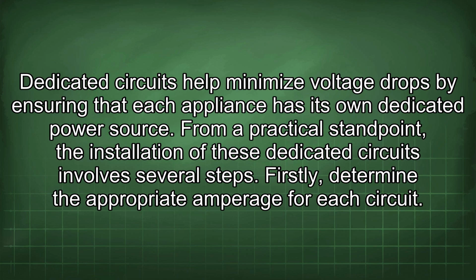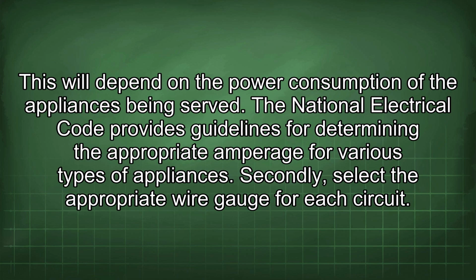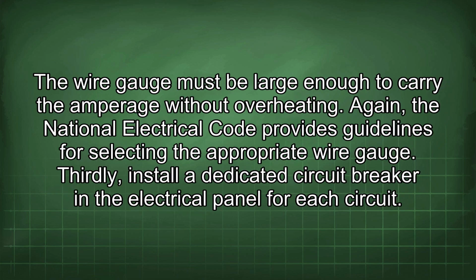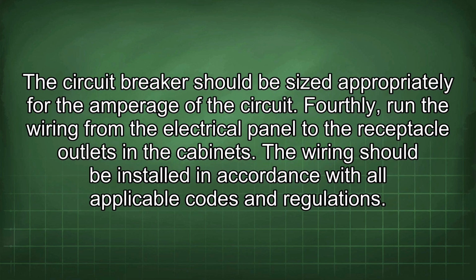From a practical standpoint, the installation of these dedicated circuits involves several steps. Firstly, determine the appropriate amperage for each circuit. This will depend on the power consumption of the appliances being served. The National Electrical Code provides guidelines for determining the appropriate amperage for various types of appliances. Secondly, select the appropriate wire gauge for each circuit. The wire gauge must be large enough to carry the amperage without overheating. Again, the National Electrical Code provides guidelines for selecting the appropriate wire gauge. Thirdly, install a dedicated circuit breaker in the electrical panel for each circuit. The circuit breaker should be sized appropriately for the amperage of the circuit.